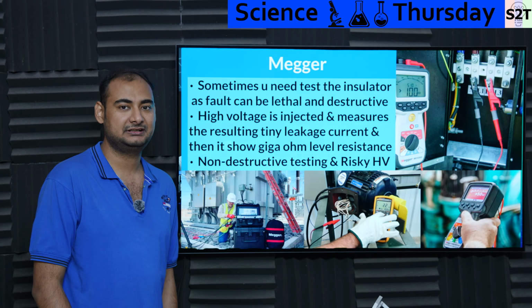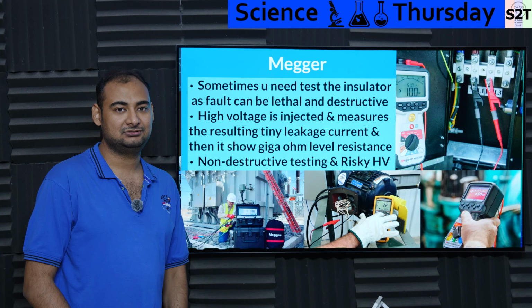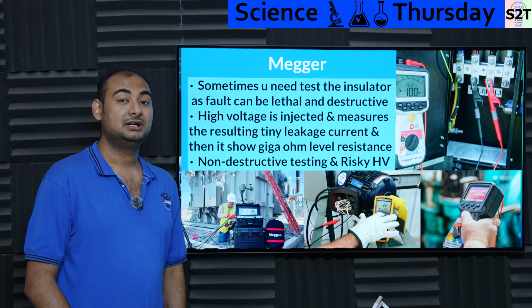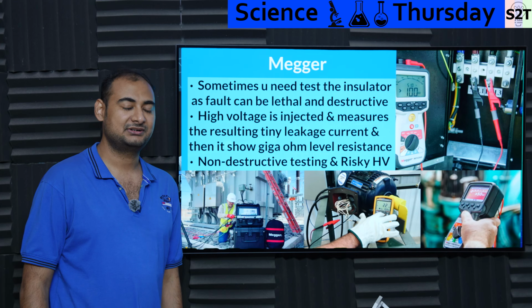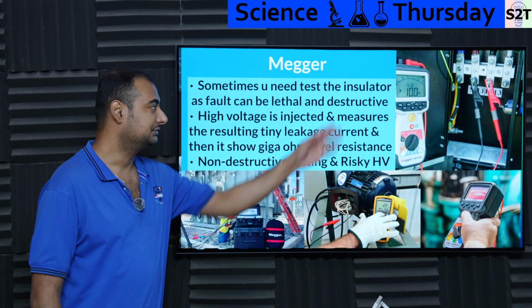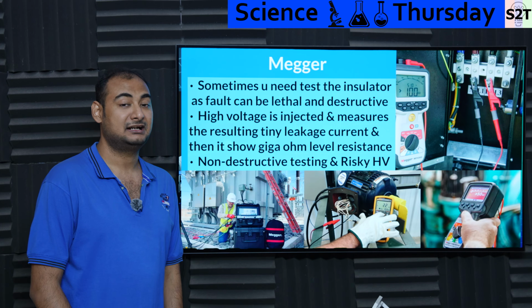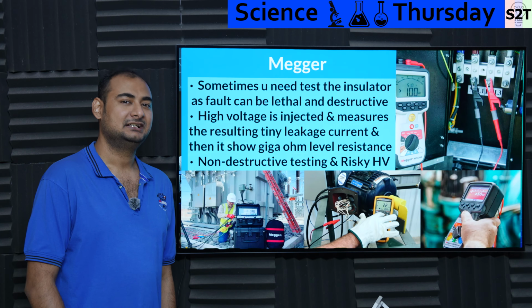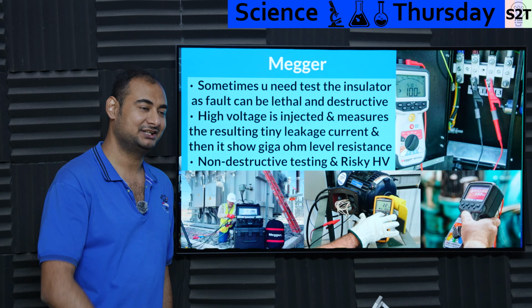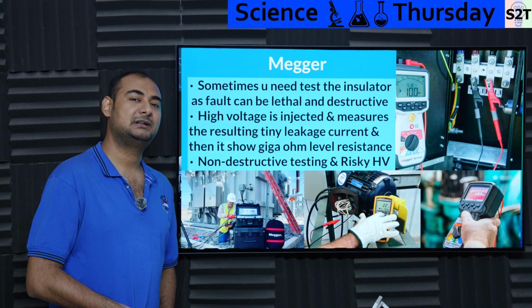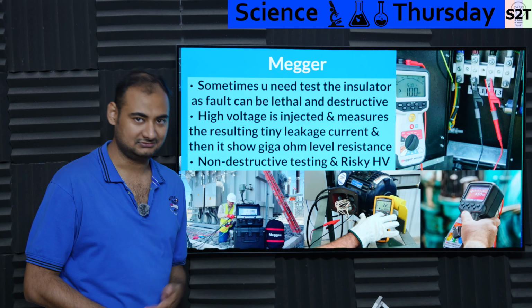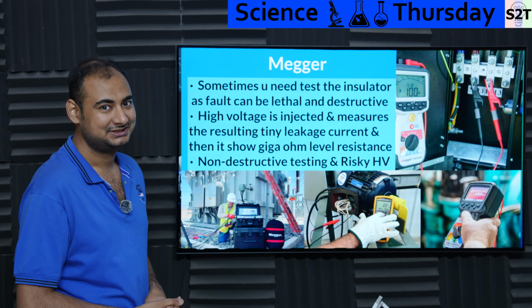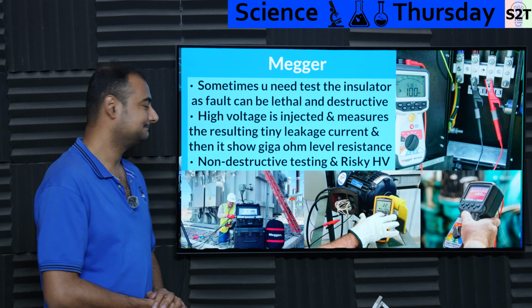How do you know it's weaker before it fails? This puppy will tell you. A healthy transformer reads 100 gigaohm -- replace the transformer if it drops to 10 gigaohm. So if it's showing 100, cool. If it starts to show 70, it's like, let's start saving money for that. If it touches 50, place the order for a new transformer, because a large transformer could take 2 years to arrive, so they place the order.